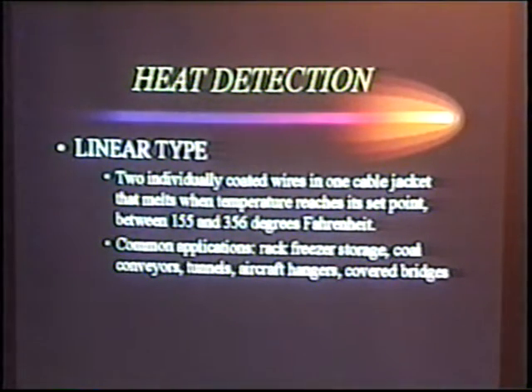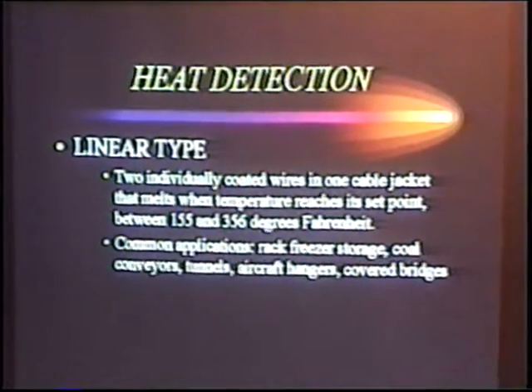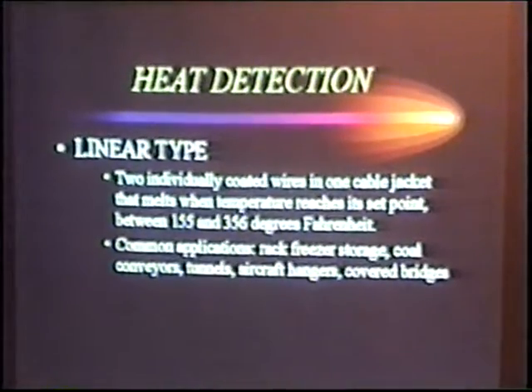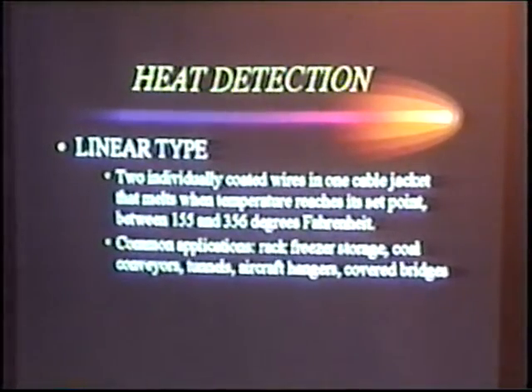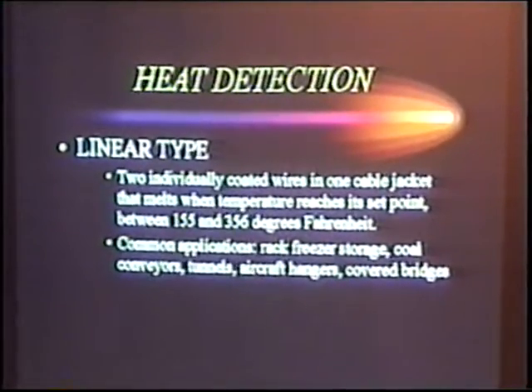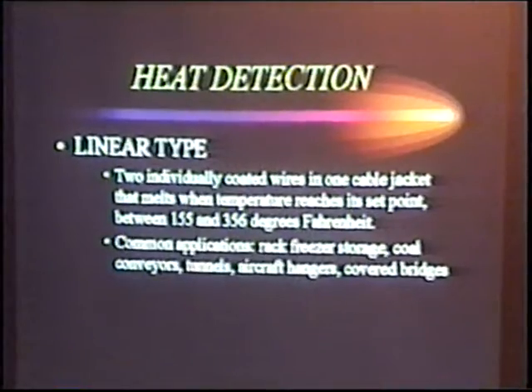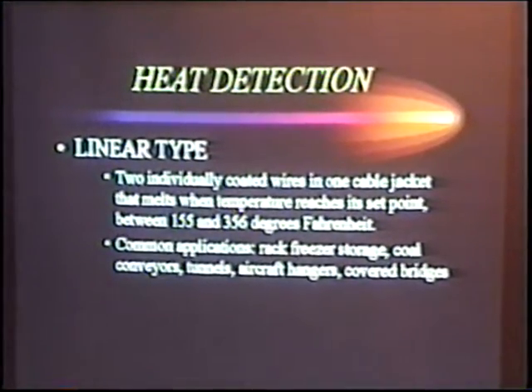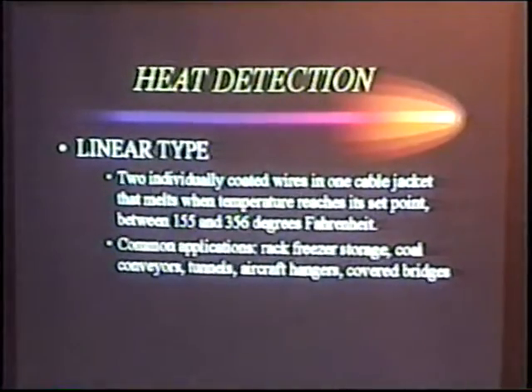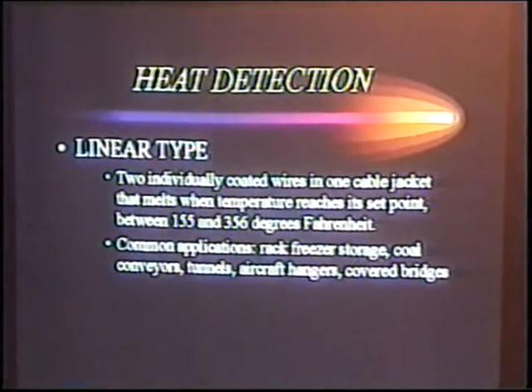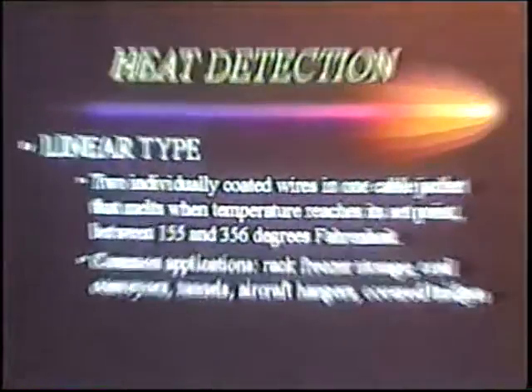With those types of systems, we're interfacing with a sprinkler system. Common applications for linear type are rack freezer storage. We do a lot of rack freezer storage around the country. So far this year, we've completed two of them where we were over 100 feet in the air. What we'll do is put linear heat detection as a separate zone up on the ceiling, and then we'll have racks that go 100 feet plus in the air. We'll have multiple levels of detection going through there. The reason this is a nice technology is that it's a lot less expensive than smoke detectors in the rack systems. Plus, in the freezer application, it's a lot easier to deal with condensation.